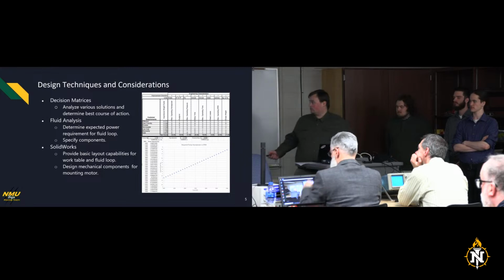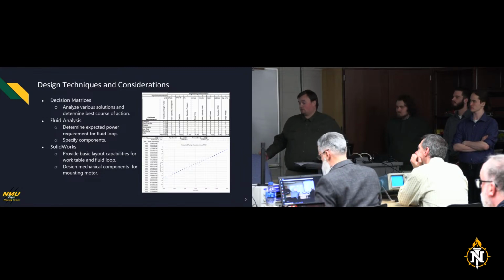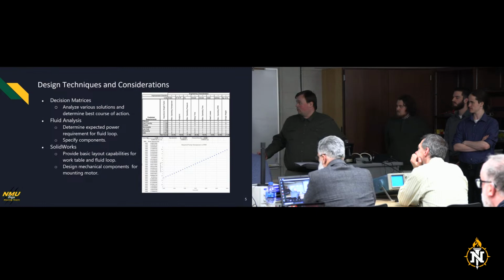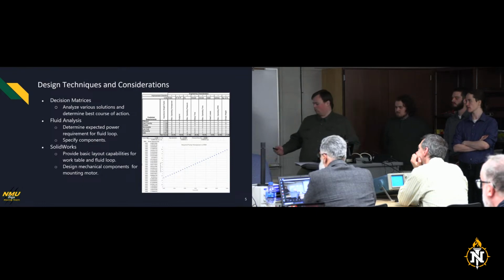So this is what we'd expect to see: with a 2000 psi pressure drop at about 3800 RPM, we'd need roughly 8 to 9 horsepower from the pump.